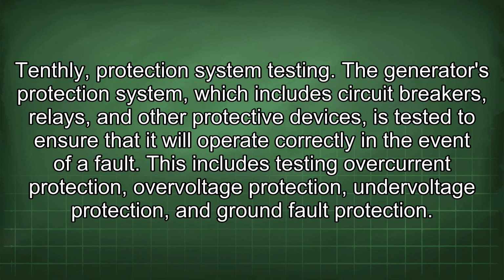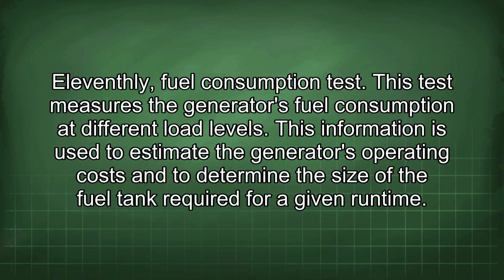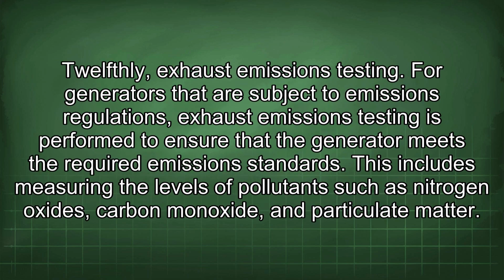This includes testing overcurrent protection, overvoltage protection, undervoltage protection, and ground fault protection. 11th, fuel consumption test. This test measures the generator's fuel consumption at different load levels. This information is used to estimate the generator's operating costs and to determine the size of the fuel tank required for a given runtime. 12th, exhaust emissions testing.